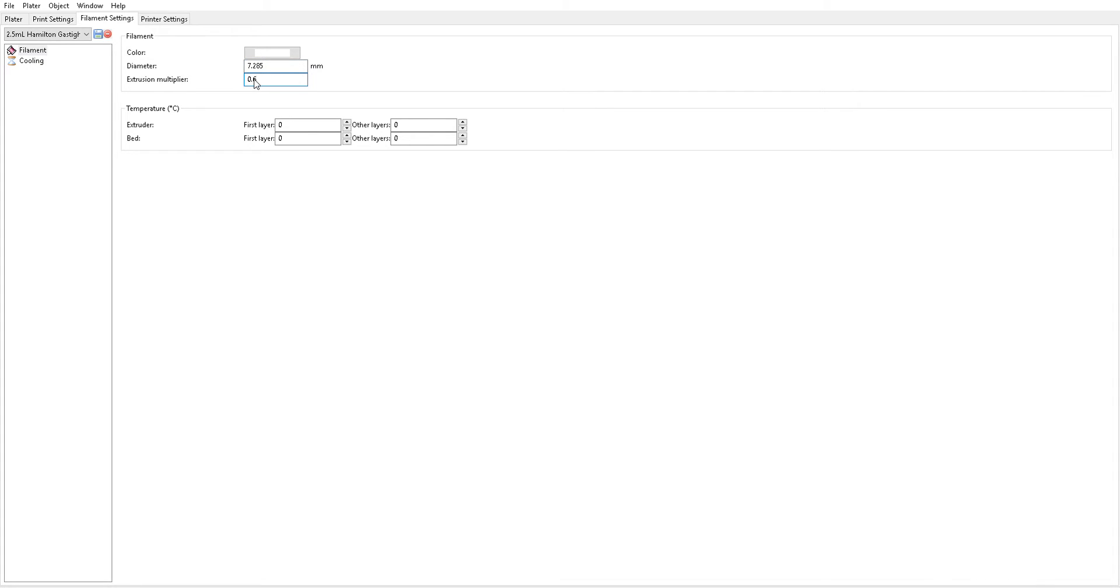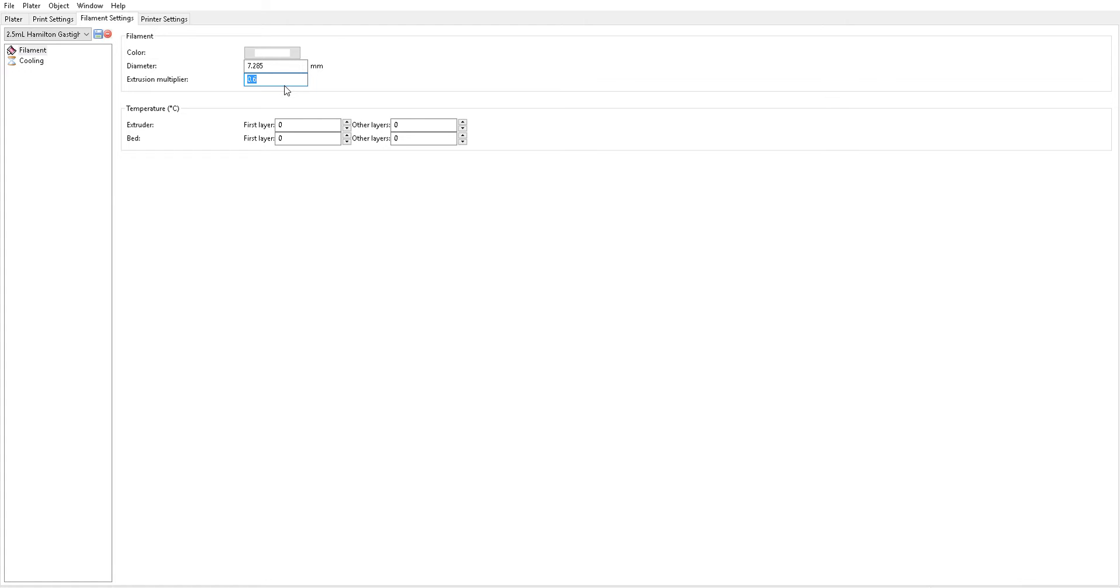And the next one that you need to have set to around 0.6 if you're doing alginate printing, this is your extrusion multiplier aka flow tweak from other slicing packages. Basically what this is saying is that once you have all of your settings filled out and the program has calculated that say to do a one centimeter edge of a cube that you need let's say one milliliter of fluid extruded, you're just saying overall I want you to multiply every extrusion that you've calculated by 0.6. So instead of extruding one milliliter it will now extrude 600 microliters. And traditionally you just do this to avoid over extrusion. It's an overall print adjustment so keep in mind that for more sensitive bits of the print it may not be the best way to go about fixing them. For alginate you want to stick around 0.6, for something like a collagen you can go up to one, we normally use 1.0, and then we go back down to 0.6 for something like a fibrin.